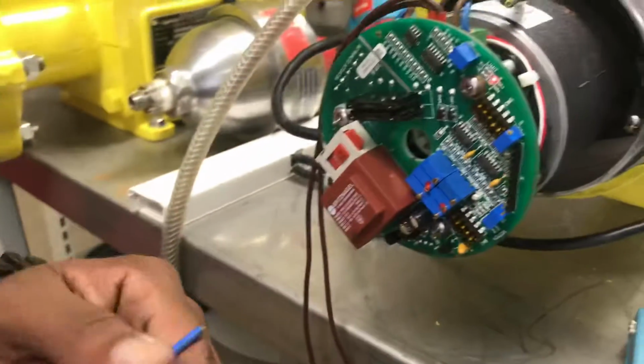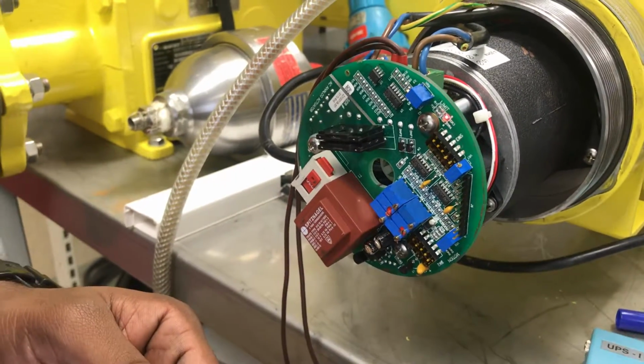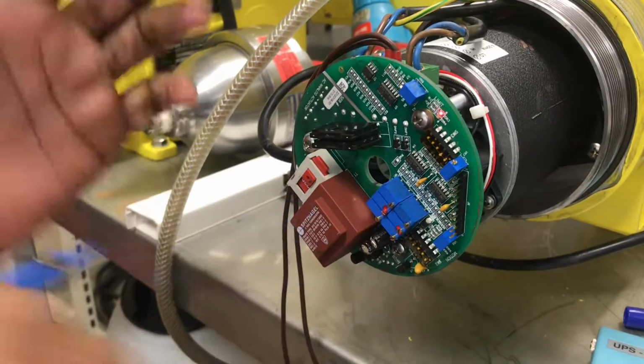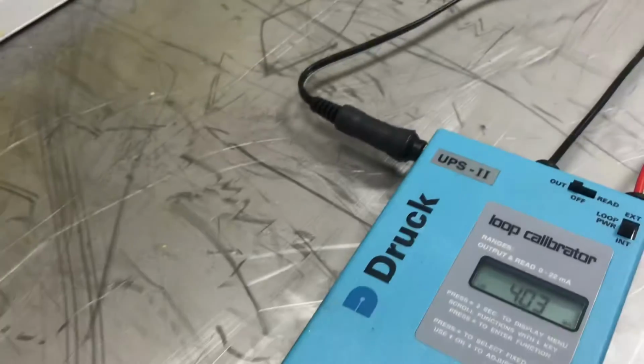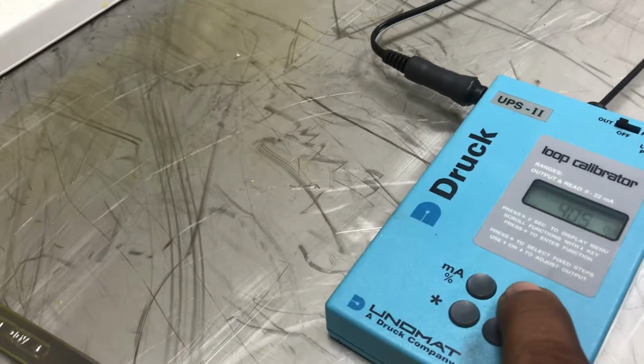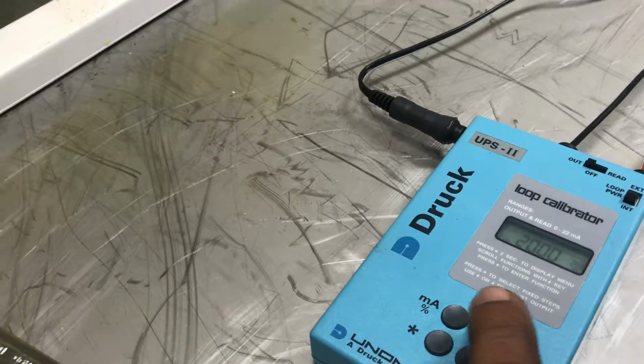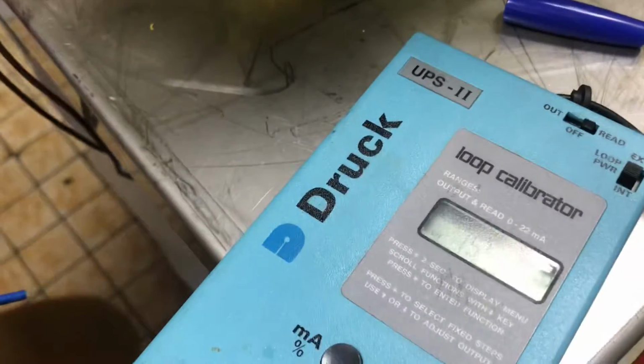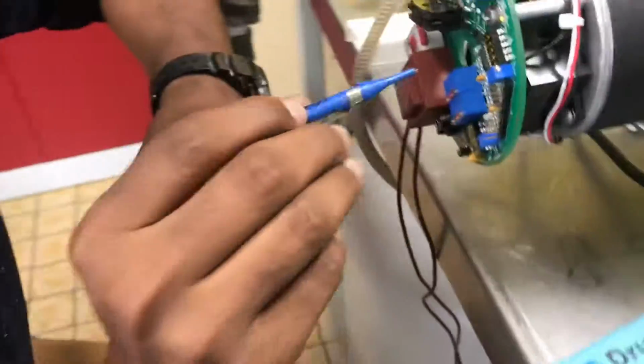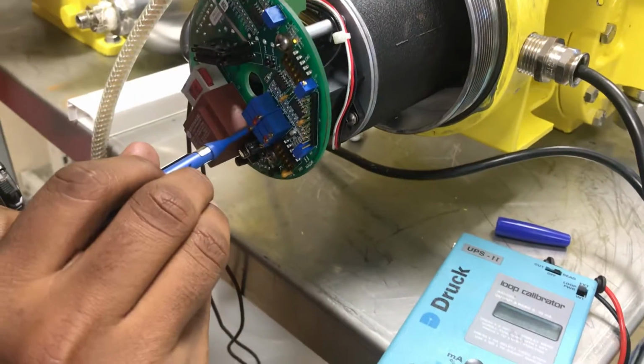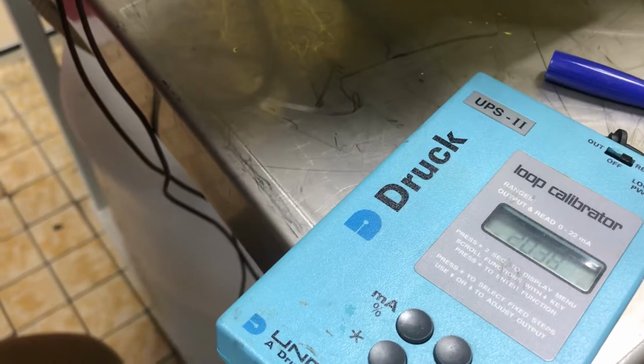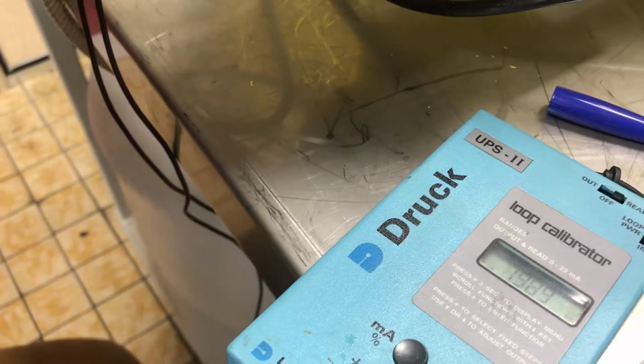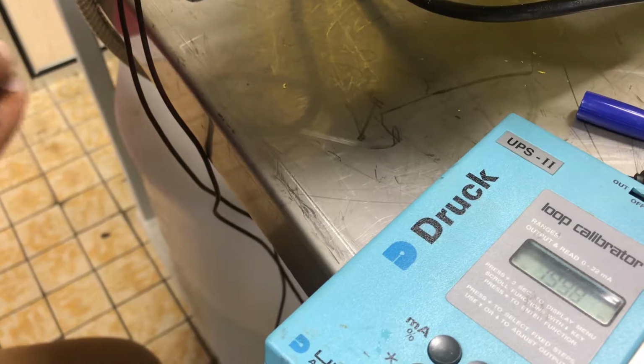Okay, 3.99 or something. Now we need to give 20 milliamps, and if it's 20.3 or something, you adjust this screw to correct the feedback. So now everything is perfect. Then you make it 100. Now it's 20.37. Now you adjust the screw slightly. Now it's 20 milliamps. So the signal is 20 milliamps and the feedback is also 20 milliamps.